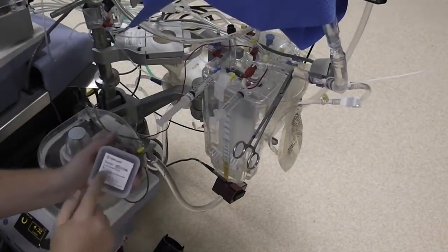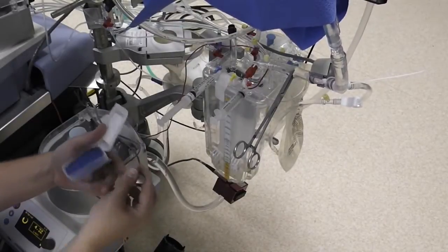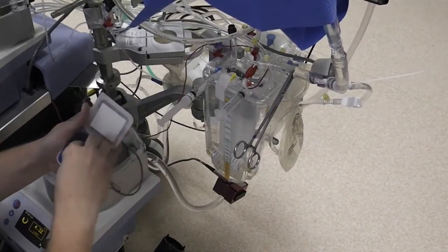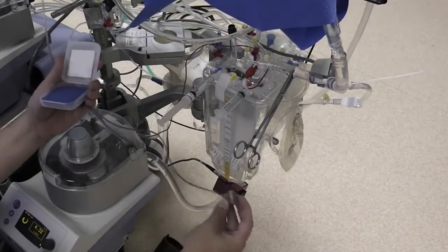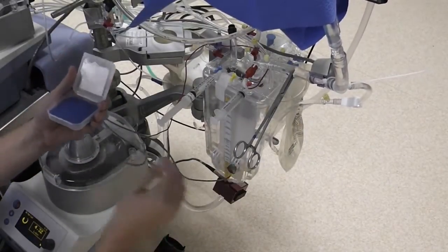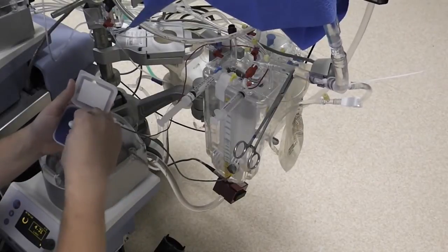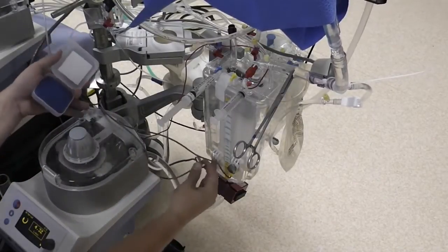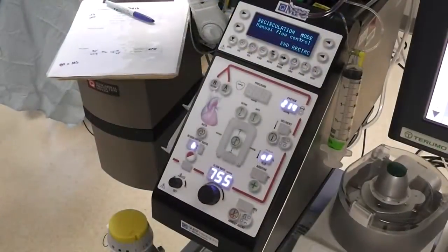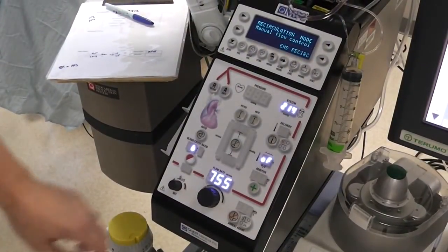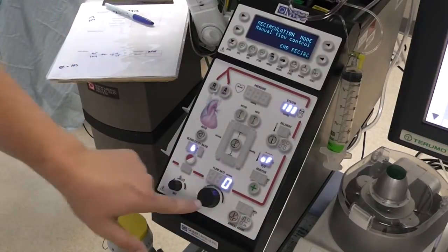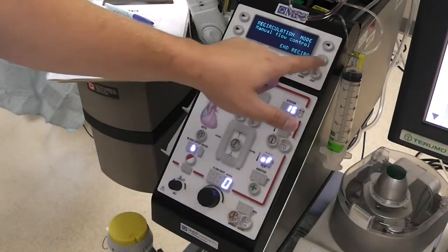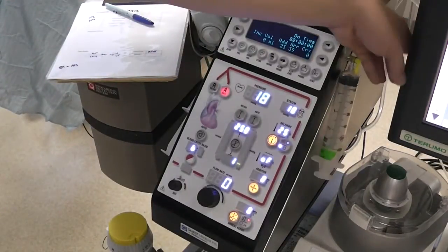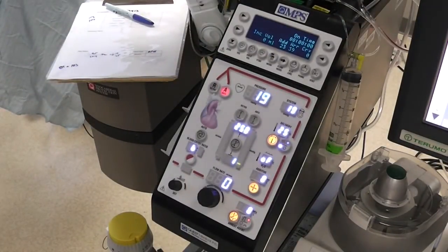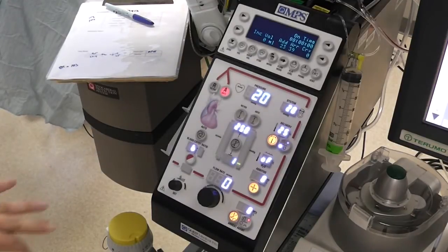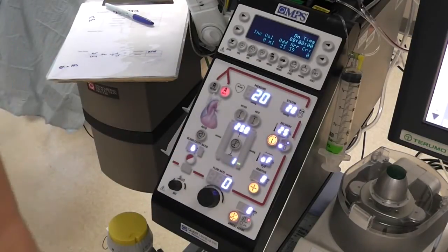To attach our level sensors, we'll need our level sensor gel. You just kind of want to dab this on each sensor. The yellow one goes on your higher level alarm, and the red one goes on the lower alarm. Okay, after your cardioplegia has been recirculating for a while, you will turn the flow rate to 0, hit end recirc. Now, if you're using the standard cardioplegia, not the Del Nido, you're going to adjust these different values now.